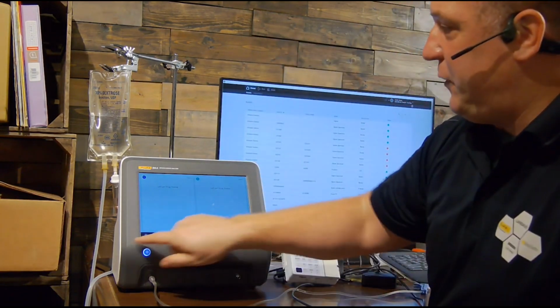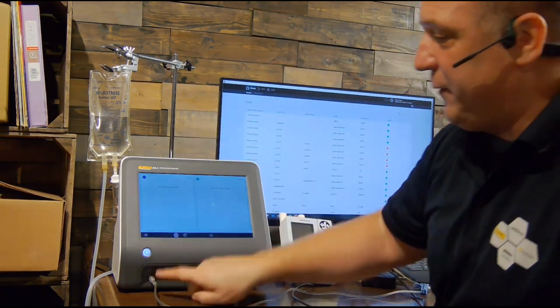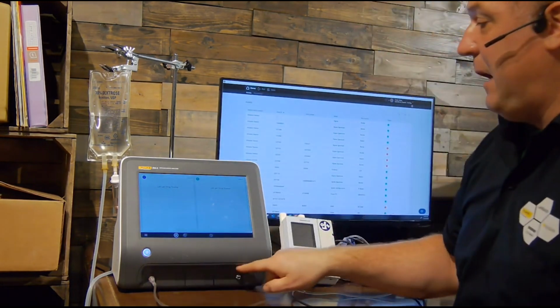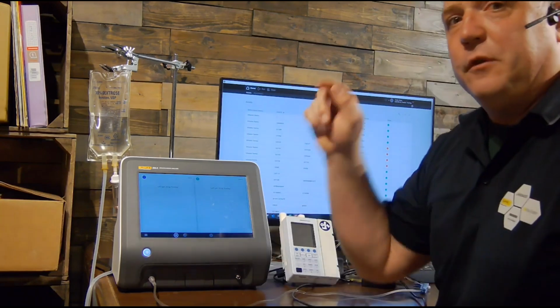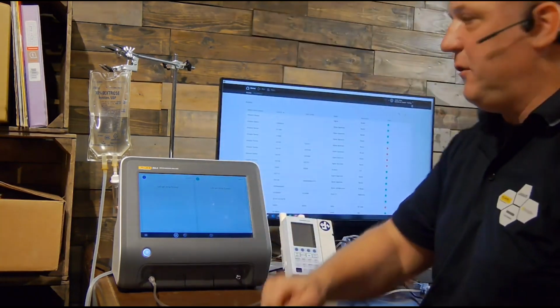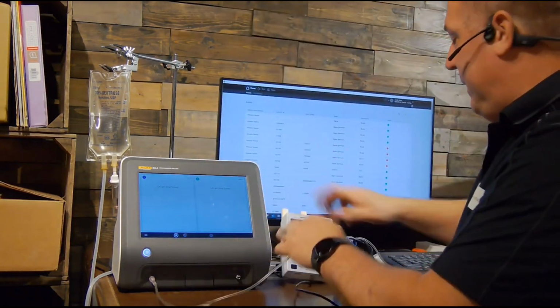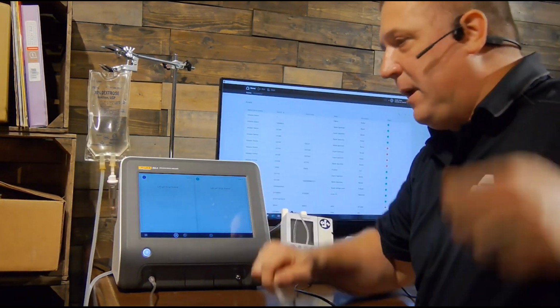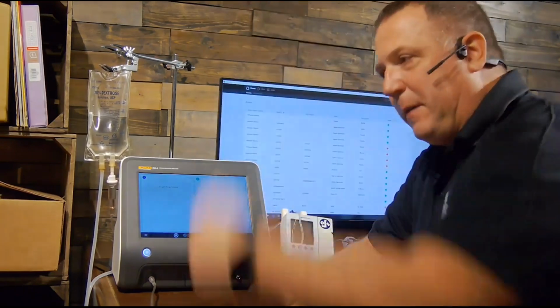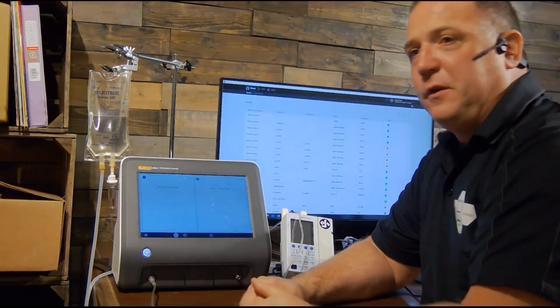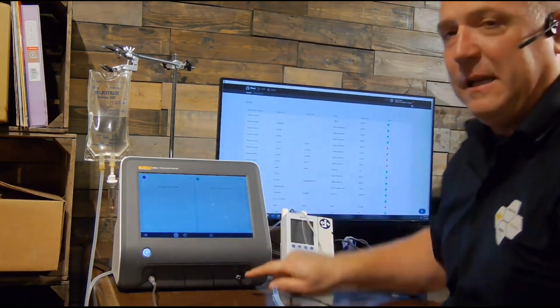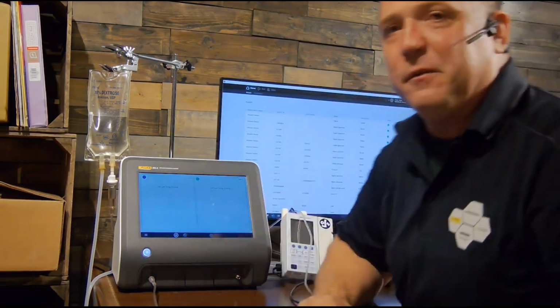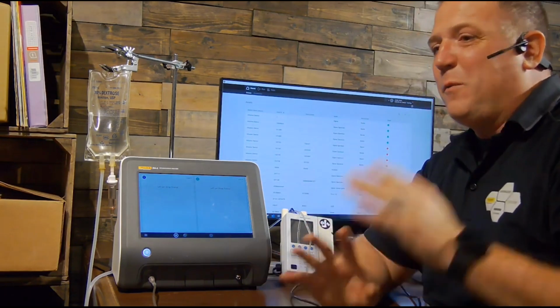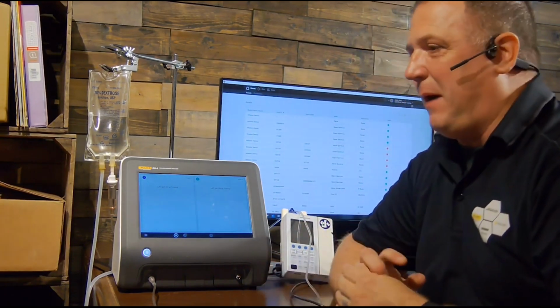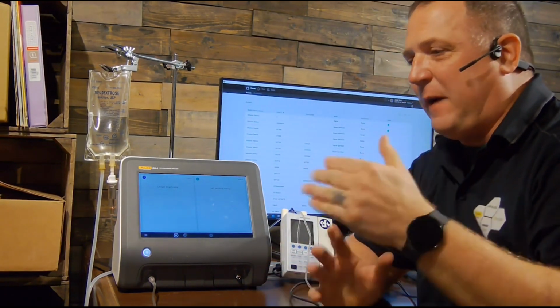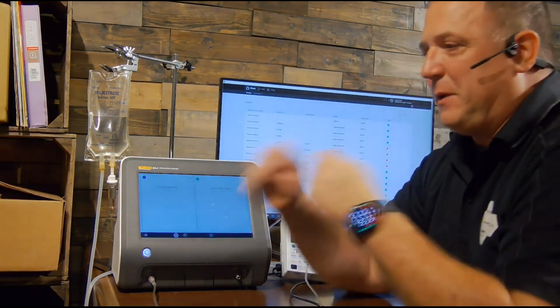So what I did is I took the 2-channel IDA-6 and I hooked my flow set to one channel and my pressure set to the other channel. When I'm doing my Alaris and going through all the procedures, the only thing I changed was my tubing. I grabbed the set for flow, put it into my infusion pump, and did my flow test. When it was time for occlusion, I took that set out, plugged in the occlusion set, and ran my occlusion test. Even there, we were saving a lot of time. I want to say like 3 to 5 minutes per pump because we didn't have to change all around.